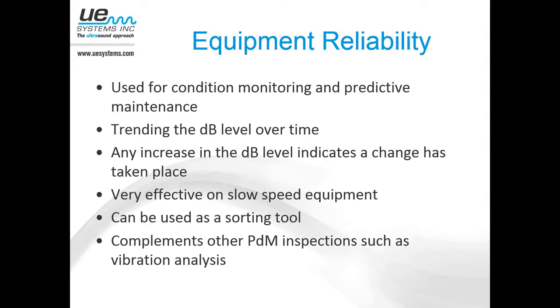Where ultrasound has proven extremely effective is on any slow speed equipment. I'd define slow speed as anything below 300 RPM, but we can get all the way down to fractional RPM. We use ultrasound on drag line bearings in mines running at a quarter RPM. Really you're just listening, not so much trending on those, just listening for any kind of click or pop as it goes around. It's extremely effective on slow-speed equipment because of the quick acquisition time. We can go out, listen, record a sound file, or just listen and make a judgment call very quickly and very accurately.